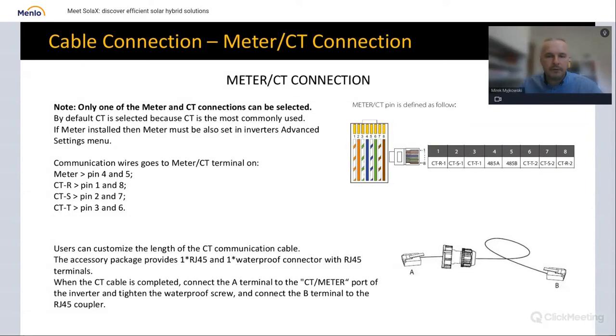With single phase it's like CTR, so it's only pins 1 and 8. The CT comes with just a short piece of wire and a connector. To make an extension, the connector looks like this, and it's supplied together with the inverter, so you can always extend this communication line from the CT into the inverter.